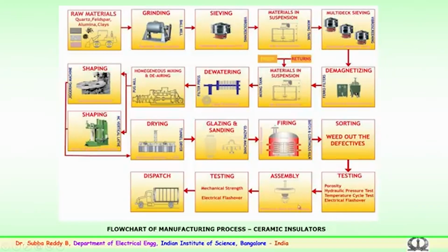Later, after the testing, comes the assembly of the insulator, which connects both the pin and the cap. Initially it is only a ceramic or porcelain shell. Now the assembly consists of a metal pin and a metal cap with the porcelain shell. After the assembly, the insulator undergoes mechanical and electrical tests in the factory. Again there is routine testing for various mechanical and electrical parameters. Finally, after the testing, a physical inspection of the insulators is done. They are packed in crates and dispatched to the required utilities. This is the ceramic flow chart for the manufacturing process.